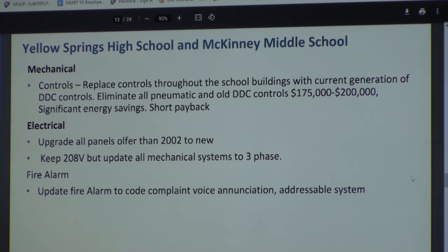And we would want to use 208 or 480 volt. The utility would want us to use 480, right? You're going to go from 1,200 amps to 1,600 amps, say, or something, it's going to be a change. At that point it would be smarter for the future of the school to be on 480, because that's fully supported by manufacturers and utilities. That's the power we're using.